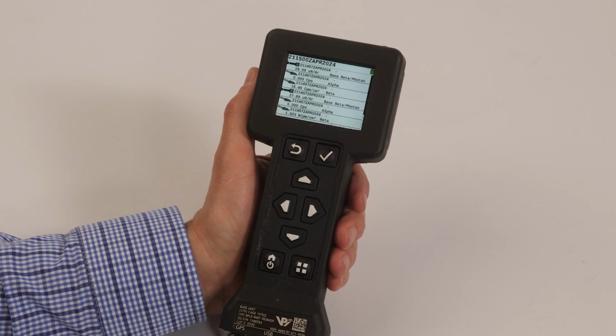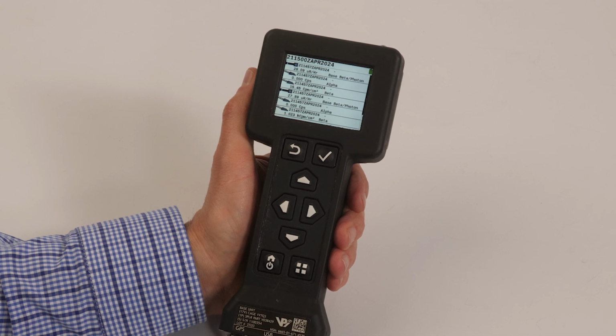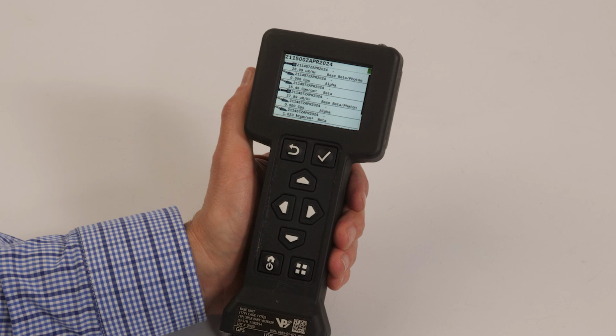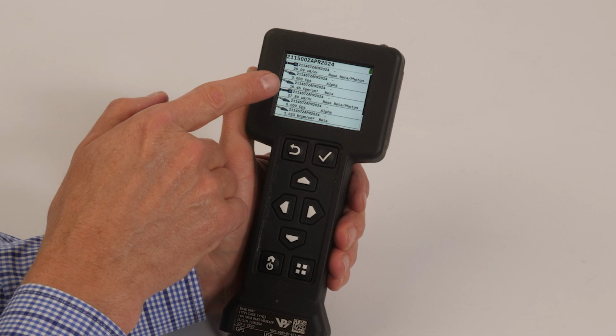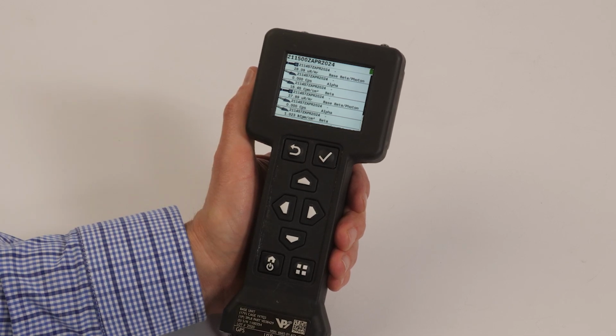Each entry is based on the interval set for the data logging mode. For example, a time interval of 10 seconds set on an auto interval data logging mode would show data entries that are captured for each 10-second interval and include the base unit and probe reading. If the probe has multiple channels, there will be a reading for every channel at each 10-second interval.